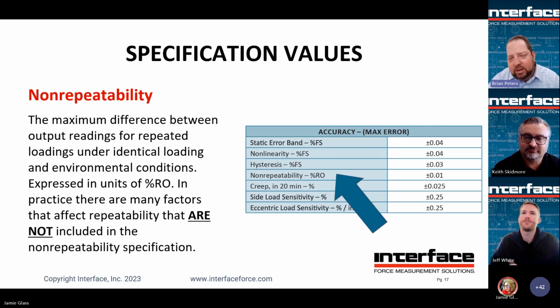So this is a specification for stability. In particular, this is something that you're really looking for from a calibration grade load cell as well. So your reference standard, you want to have really good non-repeatability so that that sensor hits the same points every time, right? Next slide.